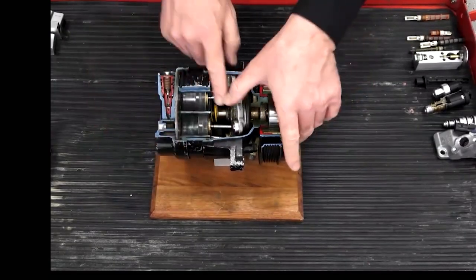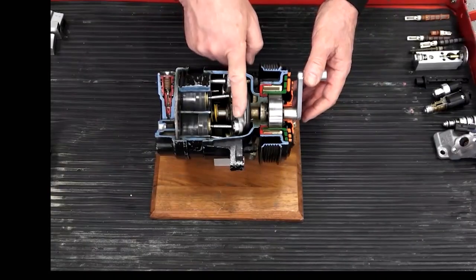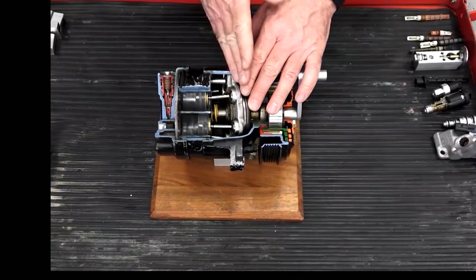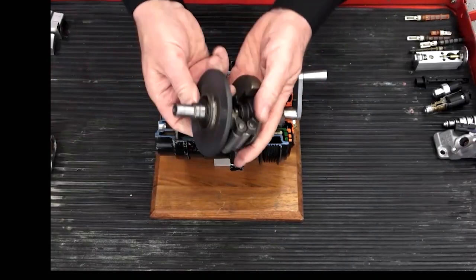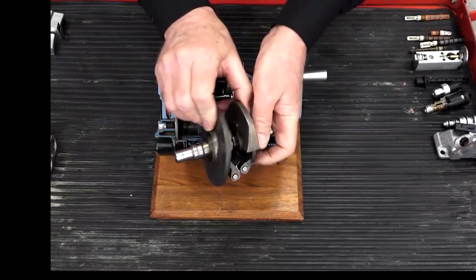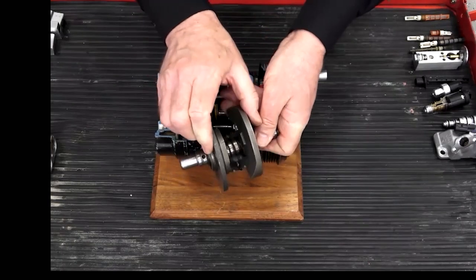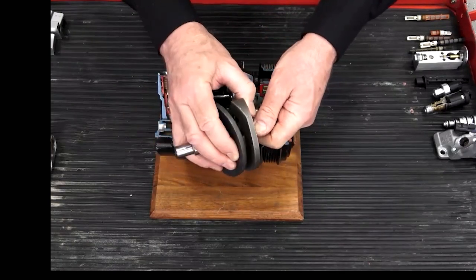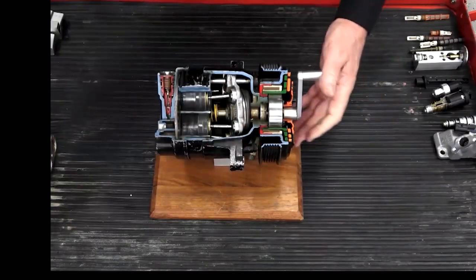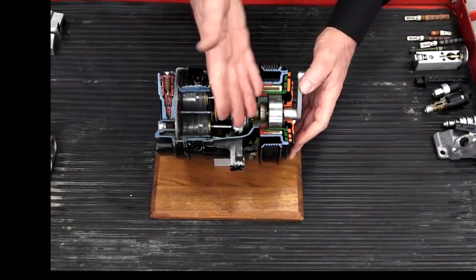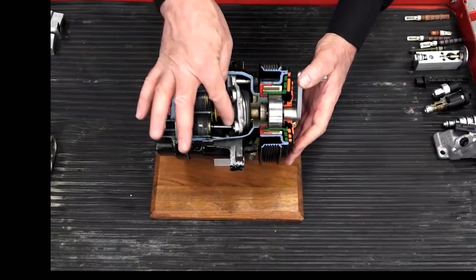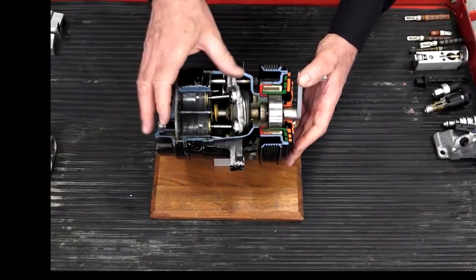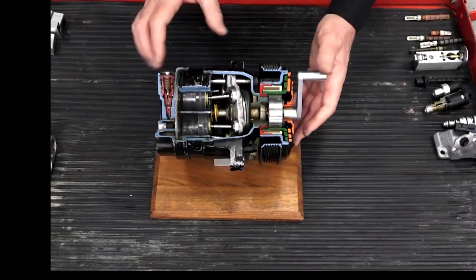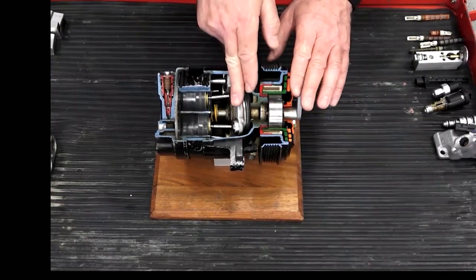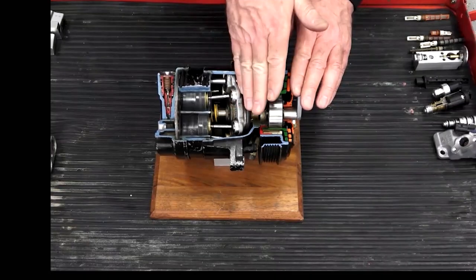Now, if you look here, this is what we call the wobble plate, or in more modern designs, the swash plate. You can see how I can change the angle of the swash plate like that. Inside this compressor, we're using a wobble plate, just the same thing, but it's got little connecting rods instead of a flat plate. And you can see the angle of that wobble plate is a pretty sharp angle.